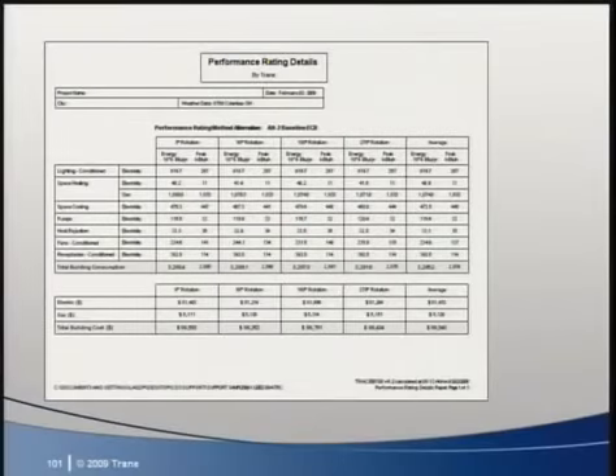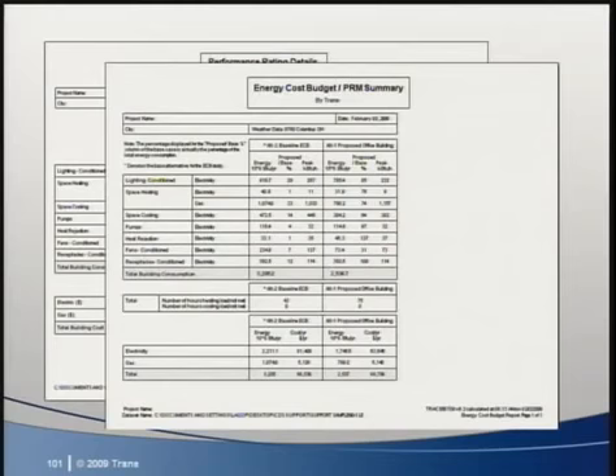Okay, let's discuss two output reports formatted specifically for LEED. The baseline energy use at each orientation is then captured and displayed on the Performance Rating Details report. The average energy use from all four orientations is then calculated and displayed on the Energy Cost Budget PRM Summary Report and compared to the proposed design alternative that the user has modeled.